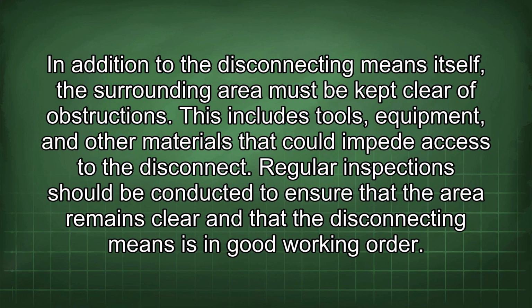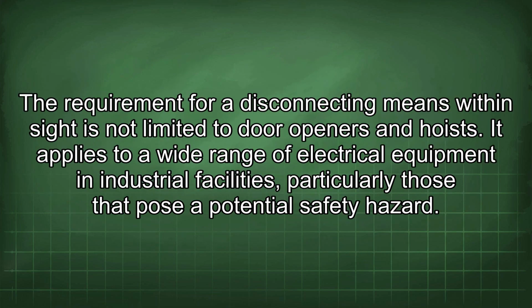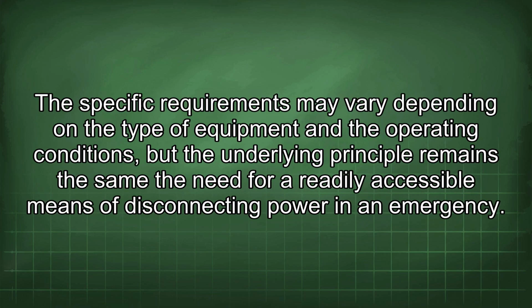The requirement for a disconnecting means within sight is not limited to door openers and hoists. It applies to a wide range of electrical equipment in industrial facilities, particularly those that pose a potential safety hazard. The specific requirements may vary depending on the type of equipment and the operating conditions, but the underlying principle remains the same: the need for a readily accessible means of disconnecting power in an emergency.